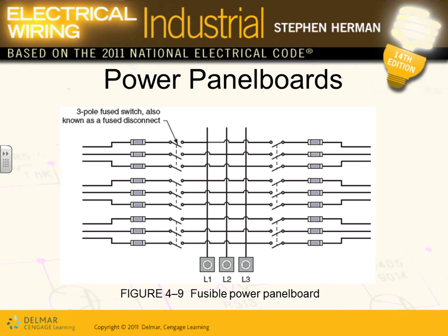Second, when they feed these fuses or circuit breakers, the first one would be phase A. So you're going to have phase A, B, C, A, B, C, and they alternate them. That's how they build them. When you're looking at a panel, single pole circuit breakers are numbered odd on the left, even on the right. So that would be 1, 2. If I ask you right now, circuit breaker 1 and 2, are they coming from the same phase? Yes.